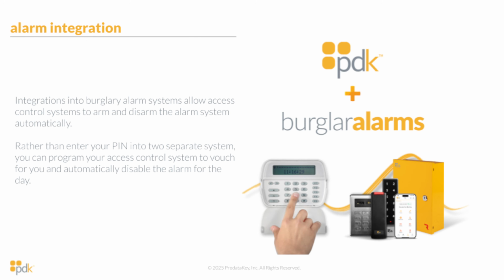So we have a full in-depth video on our YouTube channel. You can look it up with PDK and burglar alarms that goes through how to wire it. I don't have that video here, but we pulled open an actual burglar alarm system and a PDK panel, and I wired the two together and then did some screenshots and screen recordings of the programming for it. We're going to go over the programming of it today, but it's fairly straightforward, right? You just tie a relay from the PDK panel into an input on the burglar alarm system.